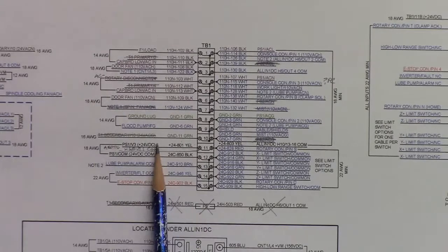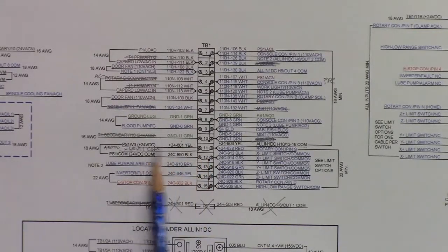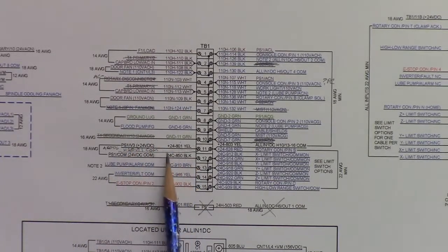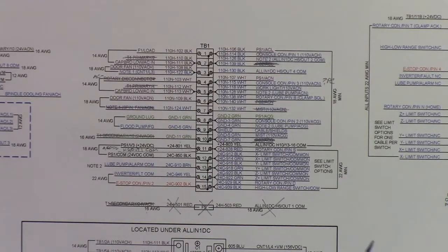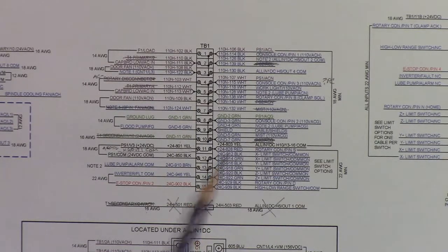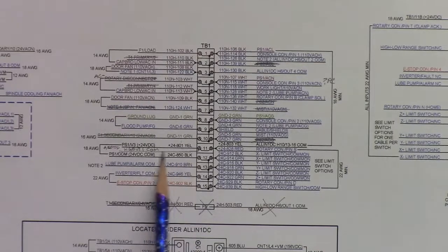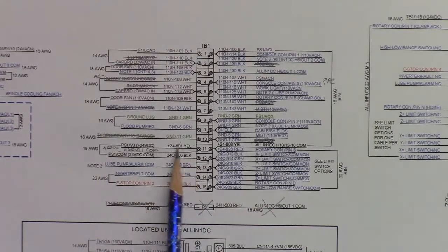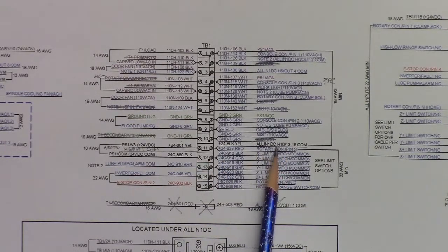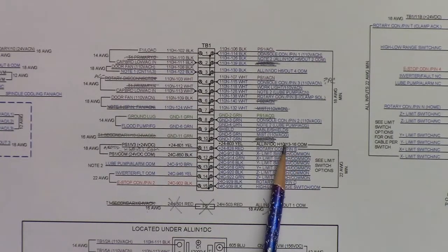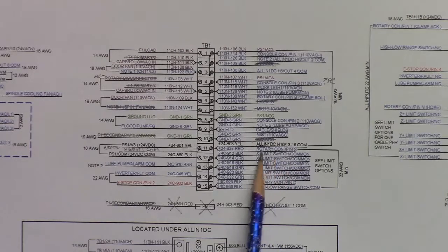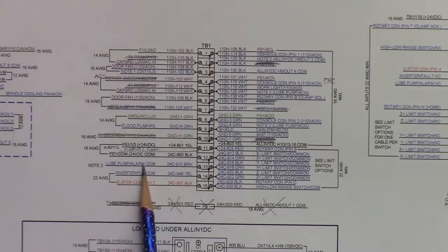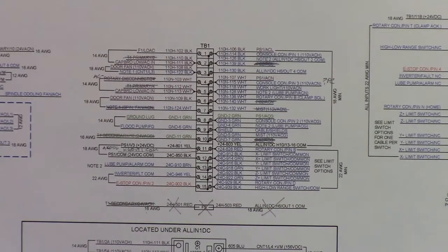I've marked out things that don't pertain to me. There's no power supply, too, in this cabinet, so I've marked that out. Moving on down here, it's just 24 volts DC. I'm using a 24 volt DC relay to activate my CNT1, my e-stop relay. They show a 24 volt AC transformer on this print, and I'm not using 24 volt AC. I didn't see the need to add yet another transformer just to activate and deactivate CNT1. So I'm using the 24 volt DC circuit, so I moved it up into the 24 volt DC.